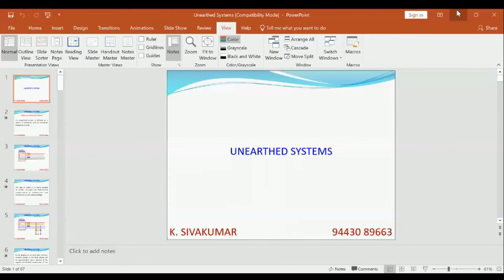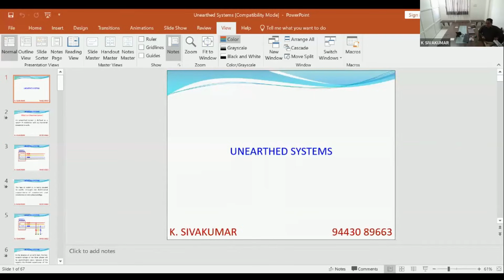So I'll take the question from Santosh. How to select the correct rating of lightning arrester for an unearthed system? See, for an unearthed system, you have to consider the rated voltage of the system. In fact, the IEC standard gives you a beautiful graph for selection of surge arrester rated voltages depending upon the R0 by X0 ratio and X1 by X0 ratio. There is a graph in the standard.